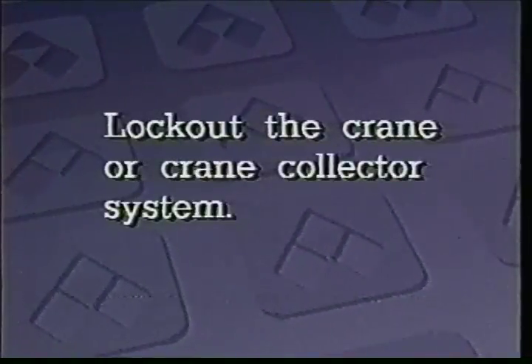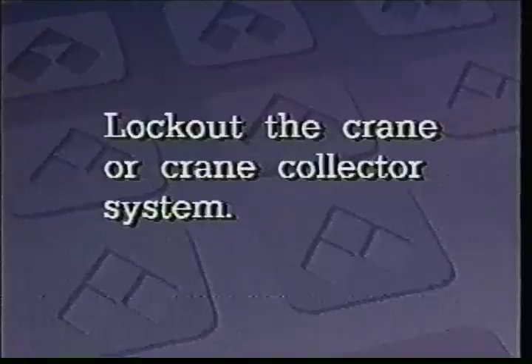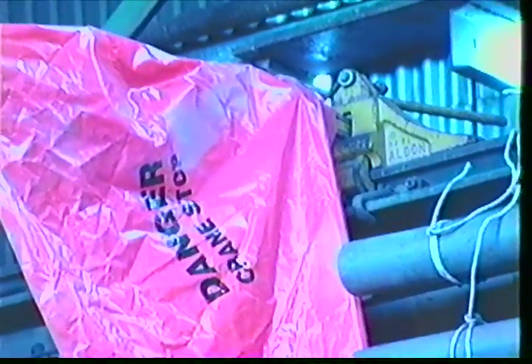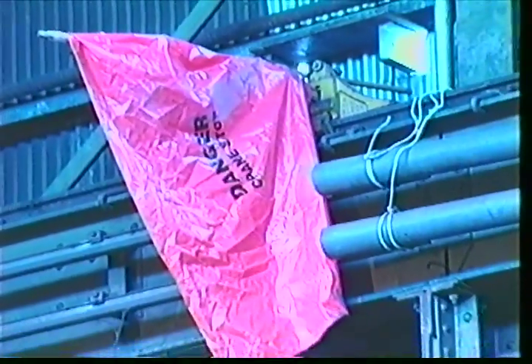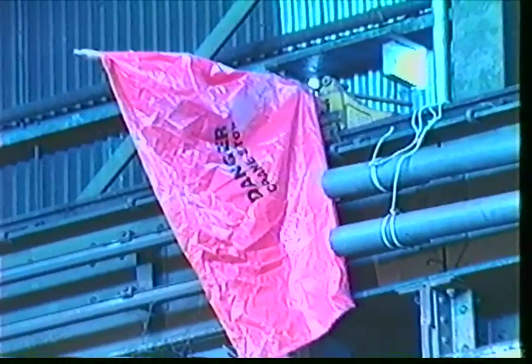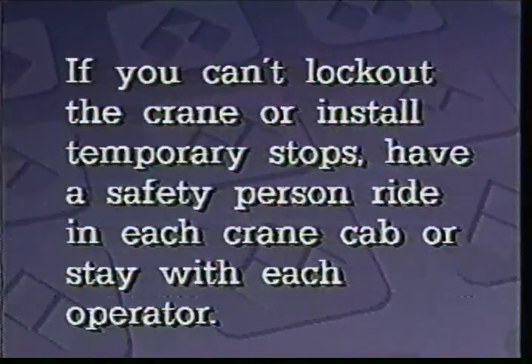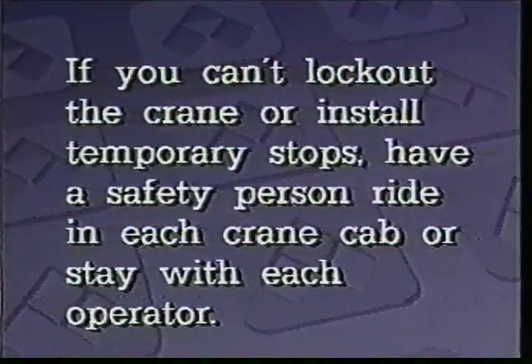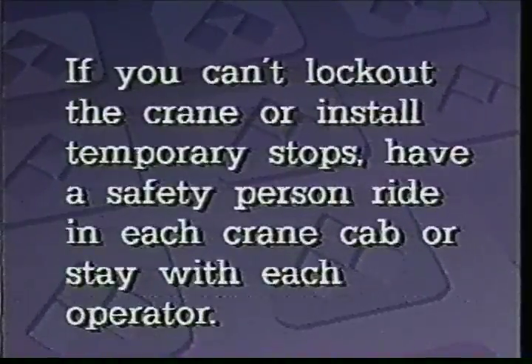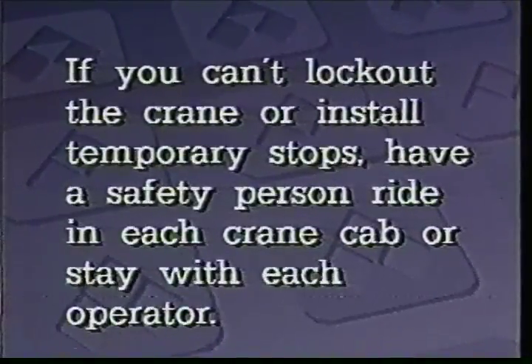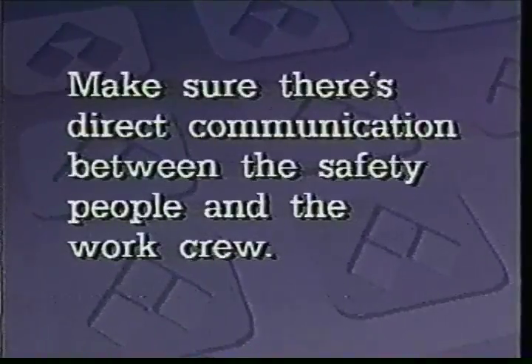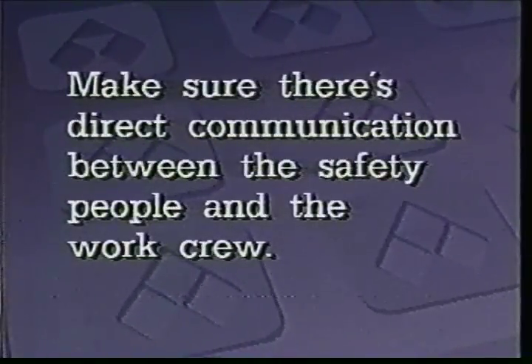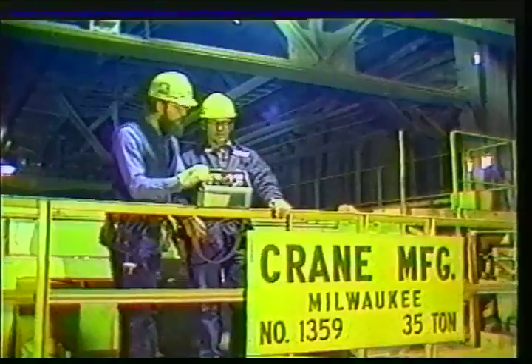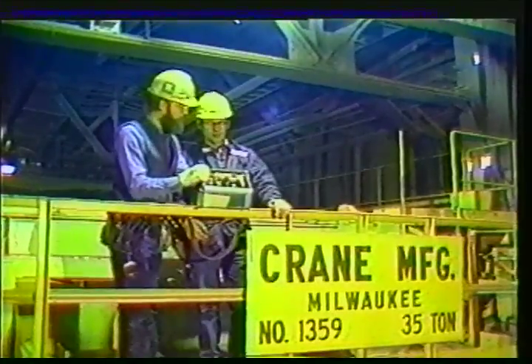Preferably, lock out the crane or the crane rail collector system. If you can't lock out the crane, install temporary rail stops and flags on the crane rails using the approved Alcoa procedures. If you can't lock out the crane or install temporary rail stops, have a safety person ride in each crane cab or with each operator. Make sure there is direct communication between the safety persons and the work crew, such as radios, lights, horns, etc.